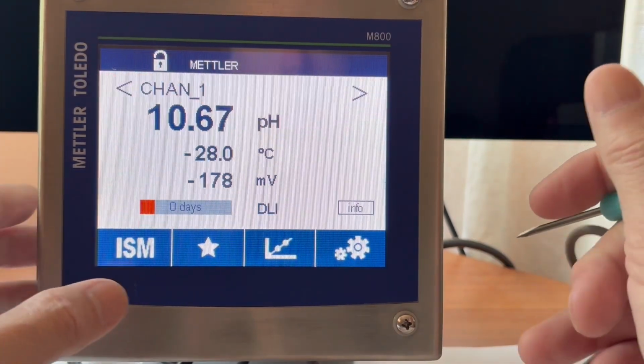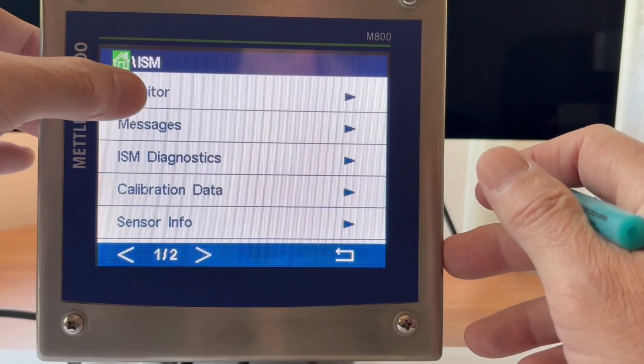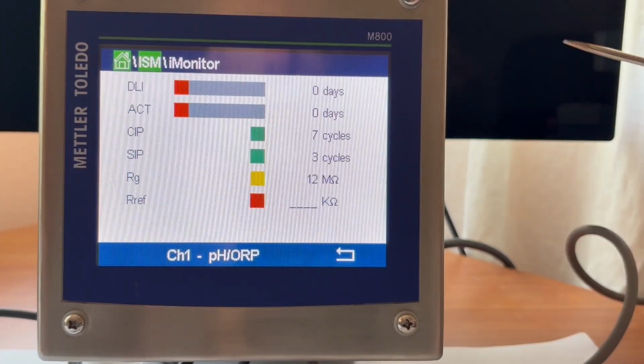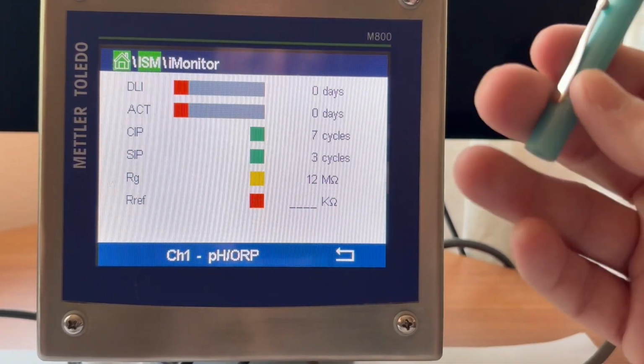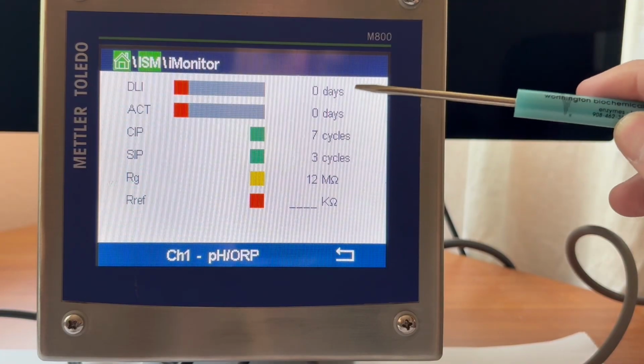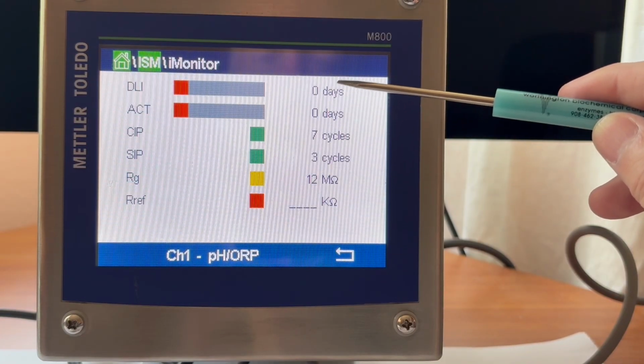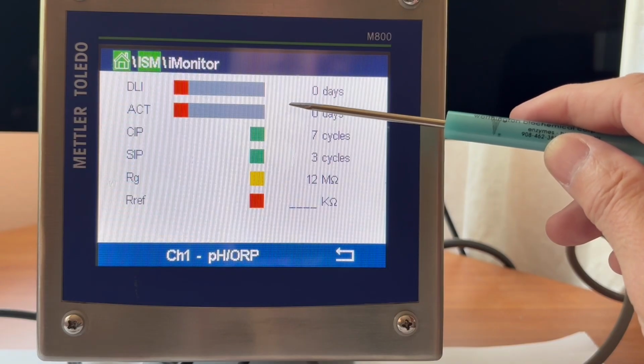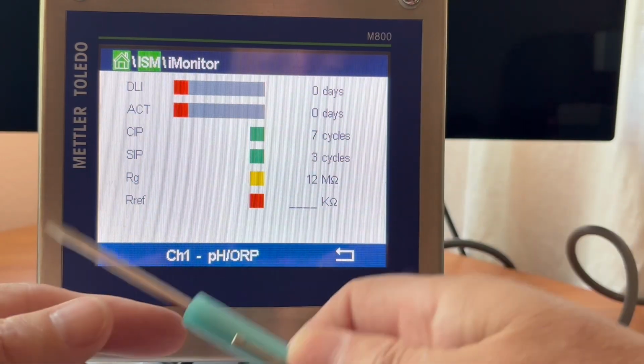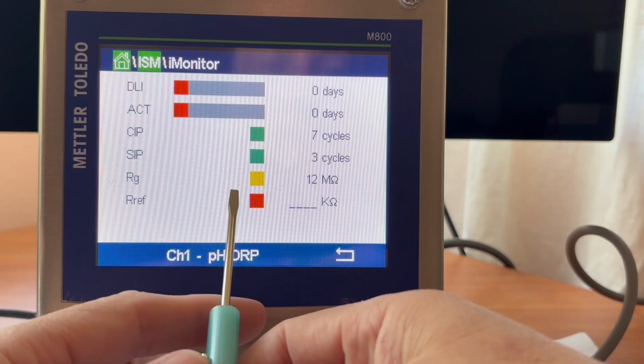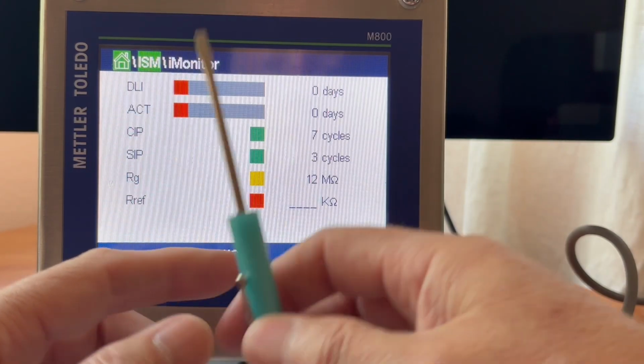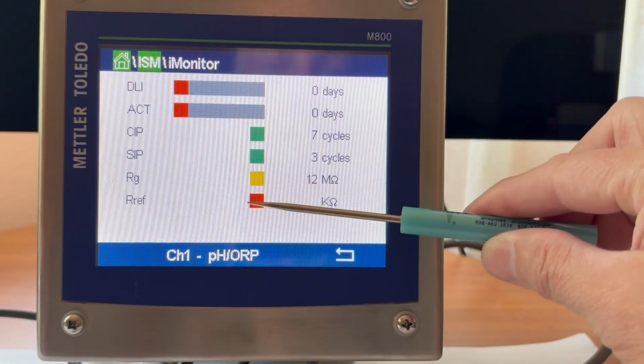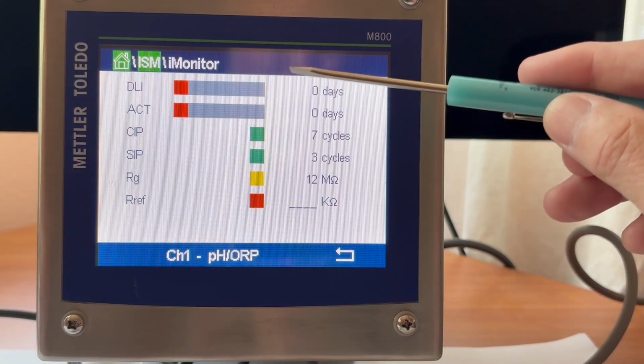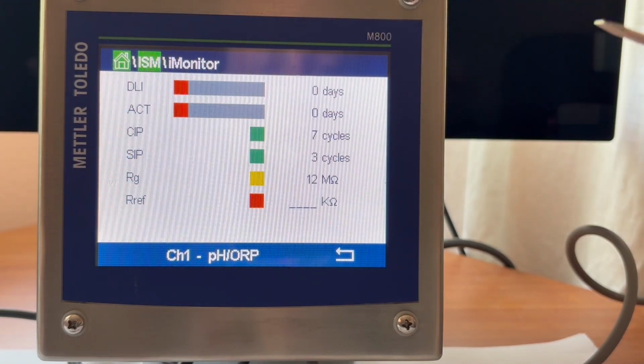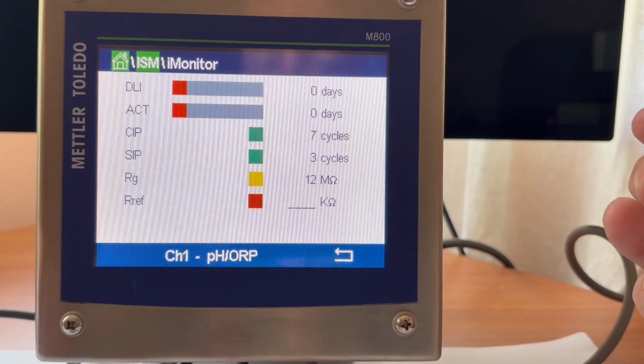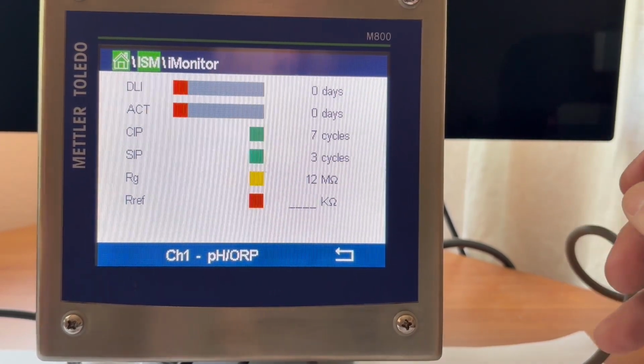If we go back here, we can see that information in the same manner under the iMonitor, but all in one view here. So we can see that the lifetime indicator says there's nothing left on this sensor. If you want to try to calibrate it, you really need to try to clean it first because your reference is shot. The glass is on its way out. And if you could improve these, you might be able to get it to calibrate. But the odds are this is indicating that the sensor has actually failed in the process and needs to be replaced.